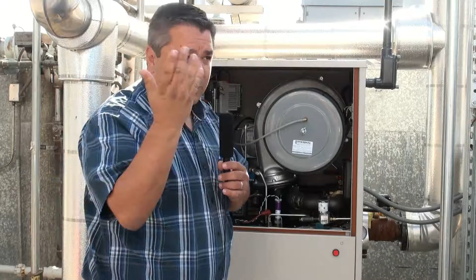If you come here and change, leave the jumper in. If you come in here and change it, it's going to validate that number until he sends it another signal to change. So you can modify the temperature all you want here locally, and it's going to accept it and move on to its endeavor. It will not go back to his number, even if he's got it at 190, until he actually sends that information back to the boiler and says go to 190.